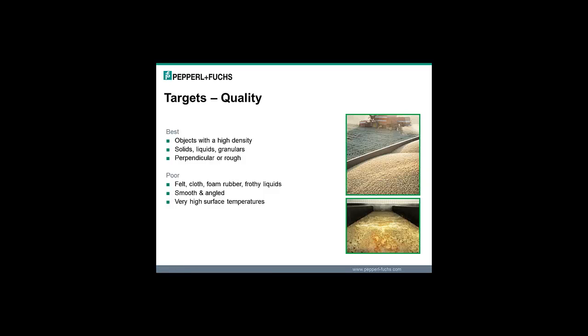Okay, we've talked a little bit about the specific standard targets that are used to measure an ultrasonic sensor's sensing range, the 1-inch diameter rod and the 100 by 100 millimeter square metal plate. But in general, in real life, you aren't going to be using those targets. You're going to be using whatever you want to sense. So the best targets, as far as quality goes, are objects with a high density. So anything solid, liquids, granulars like rocks, like corn, whatever, just things with a high density. And whether the target is perpendicular, that's obviously the best. You're getting the maximum sound back for your echo.